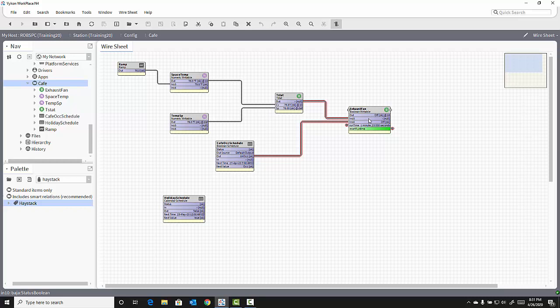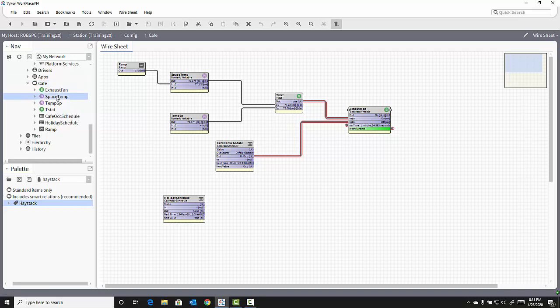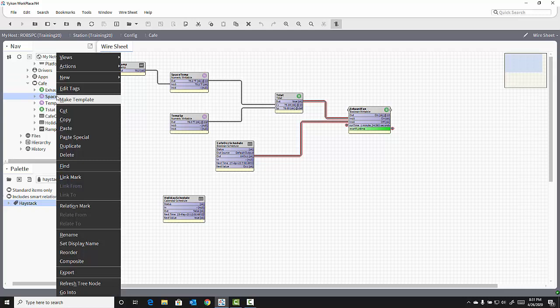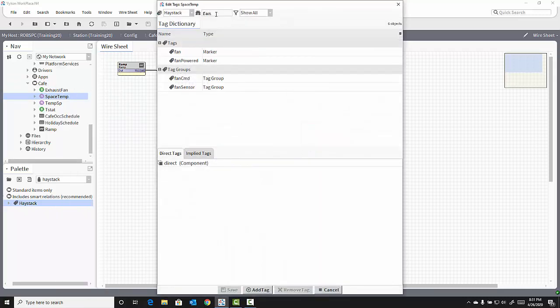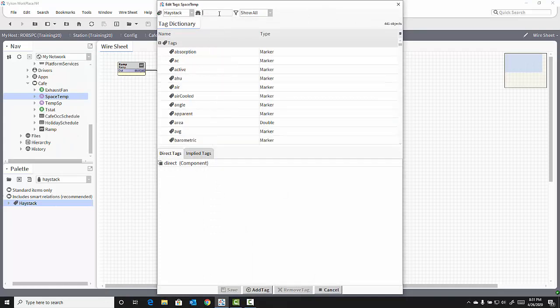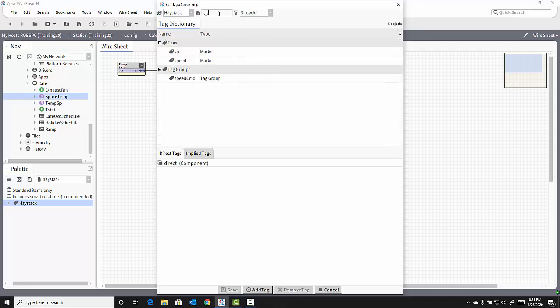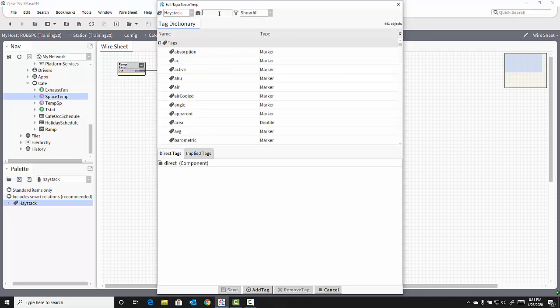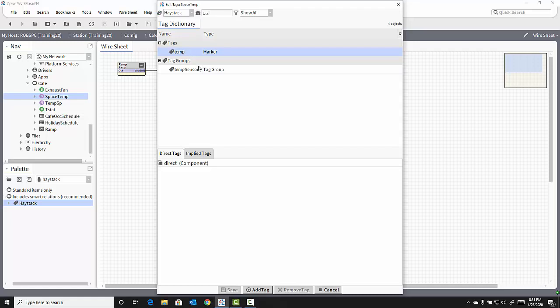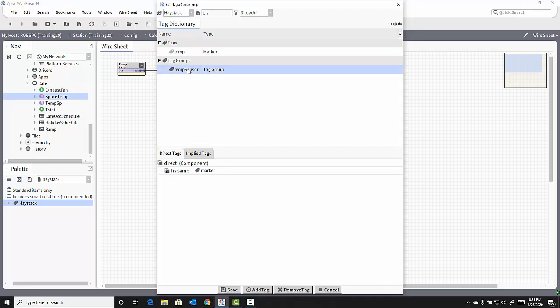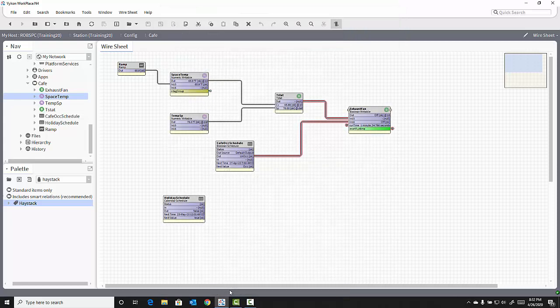Let's add a couple more tags within this cafe wire sheet. I'll add a temp tag to my space temp sensor. I can do this directly in the nav tree by right-clicking on space temp and selecting Edit Tags. Notice the fan is still in the filter field. Instead, I'm going to delete that and filter for temp. And notice I have a temp marker tag or a temp sensor tag group. Let's add both of those to our space temp object and click Save to add the tags.